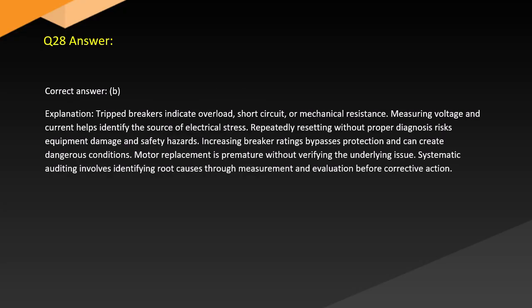Answer. Correct answer. B. Explanation. Tripped breakers indicate overload, short circuit, or mechanical resistance. Measuring voltage and current helps identify the source of electrical stress. Repeatedly resetting without proper diagnosis risks equipment damage and safety hazards. Increasing breaker ratings bypasses protection and can create dangerous conditions. Motor replacement is premature without verifying the underlying issue. Systematic auditing means identifying root causes through measurement and evaluation before corrective action.